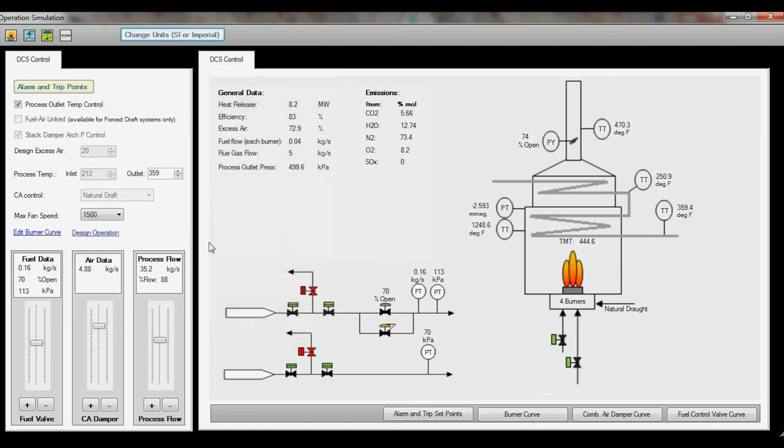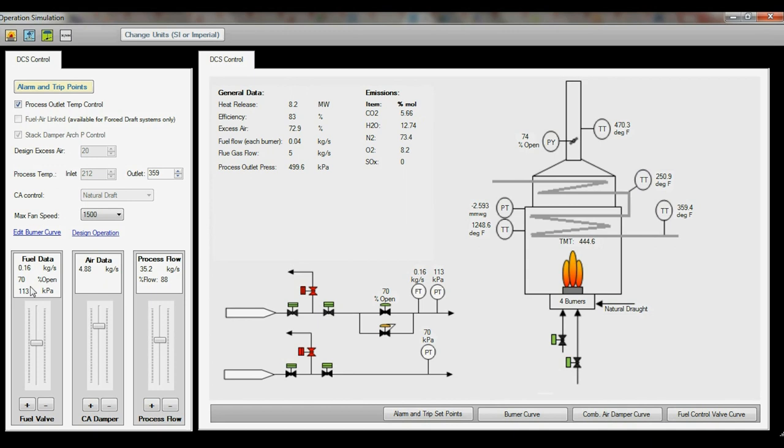The basis of simulation can also be adjusted by ticking the outlet temperature control loop and linking the fuel air ratio control, which is only available for forced draft heaters.